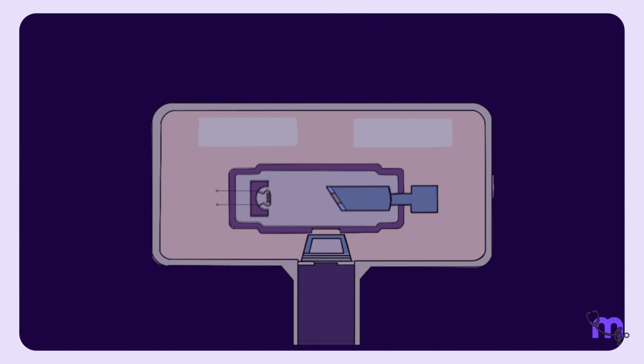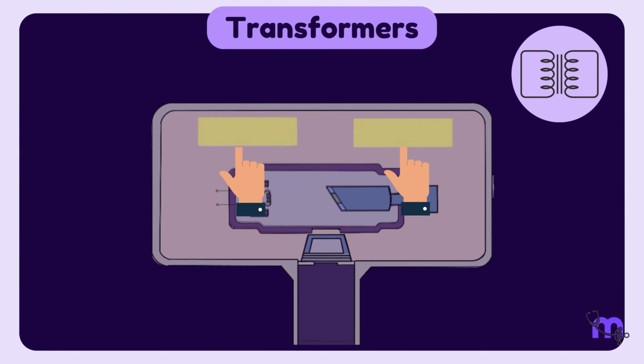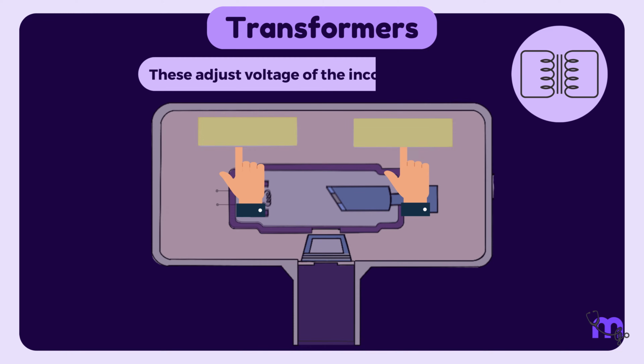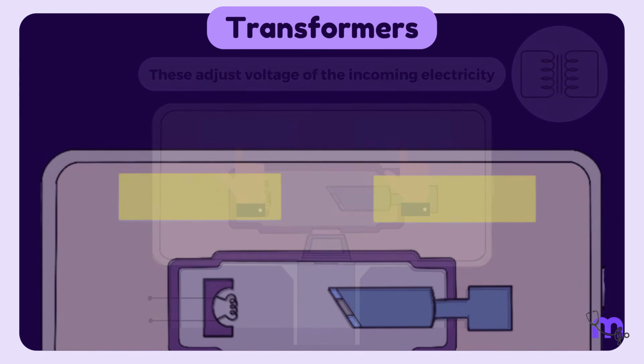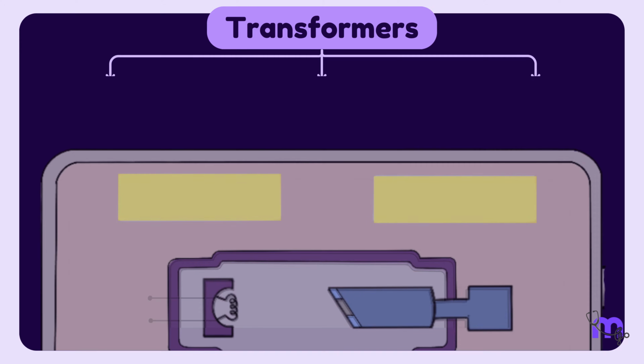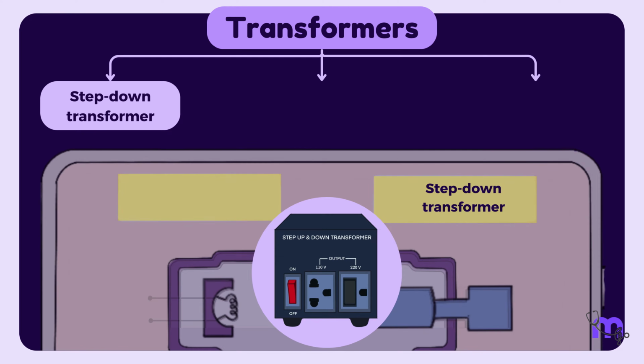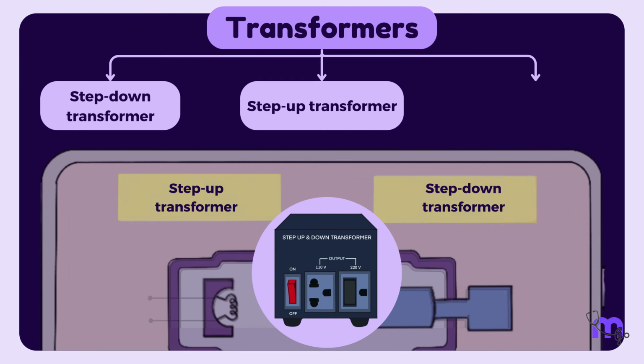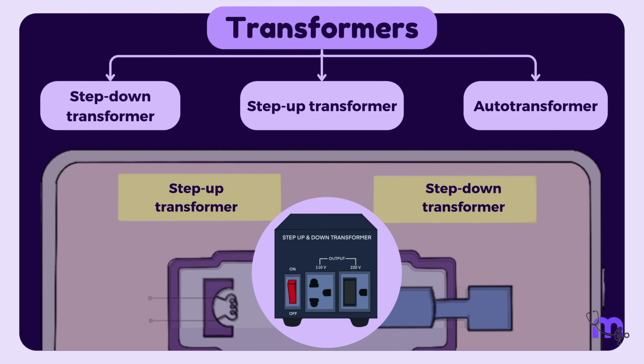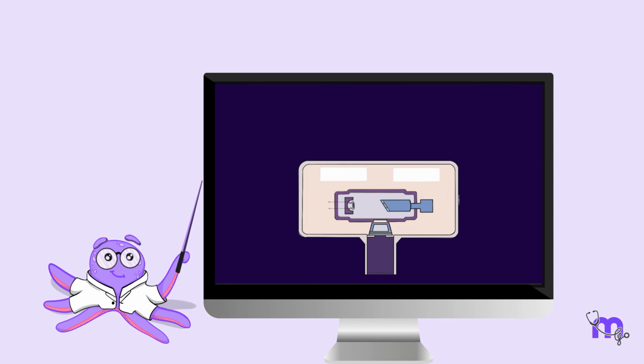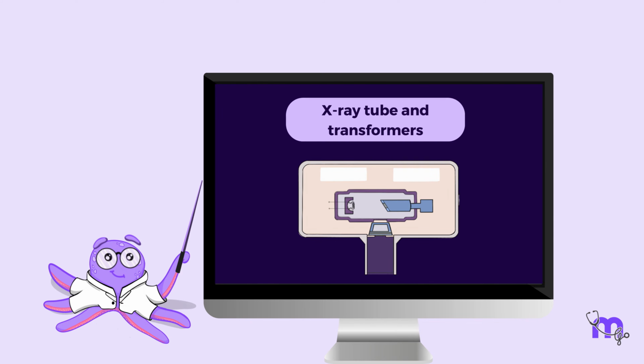To power the X-ray tube, transformers are housed within the tube head. These devices also adjust the voltage of the incoming electricity, ensuring efficiency for X-ray production. They can be of three types: the step down transformer, the step up transformer, and the auto transformer. Further details about the X-ray tube and transformers will be discussed in our subsequent videos.